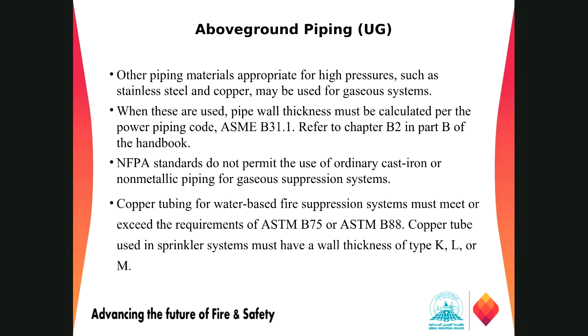And if you are using copper tube for the water-based fire suppression system, it shall be as per ASTM B75 or ASTM B88. And the thickness should be as per Type K, L, or M for fire protection applications.